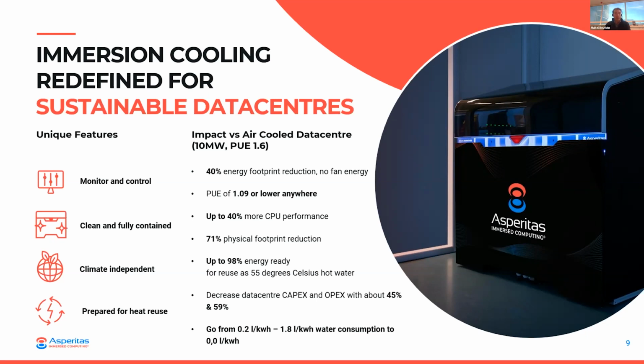It starts with the IT power demand. To keep the case very simple, what we don't use are fans in the server. We see an average of about 12% of IT power, on the server side, being utilized by the fans alone. That's significant - there's a win on day one when we apply immersion cooling in any case. So even if the facility is not optimized or the environment is not ideal, this can still be achieved on day one.